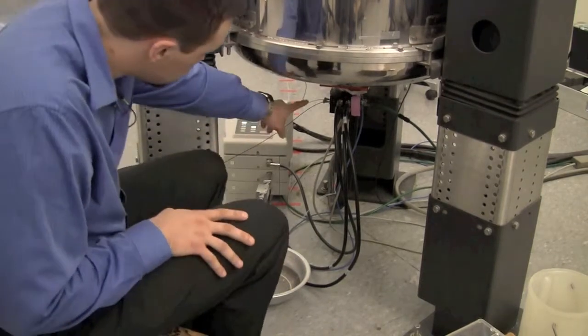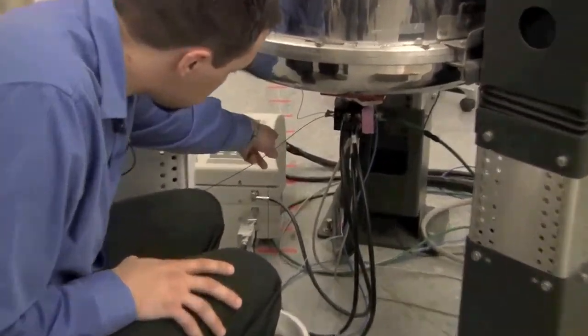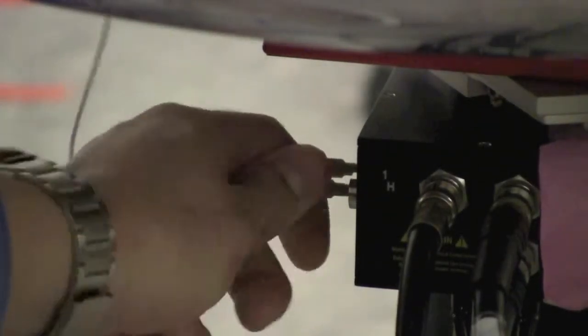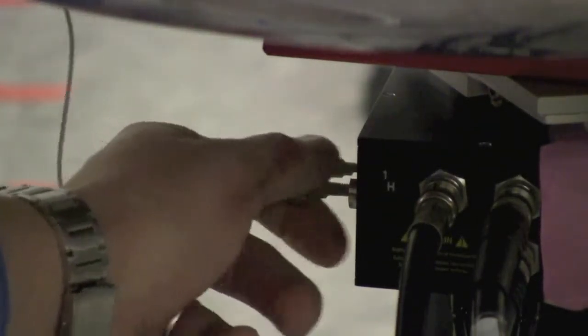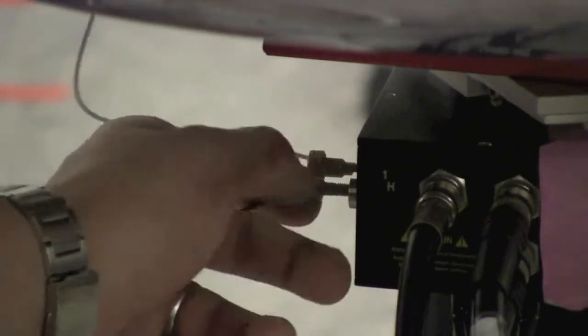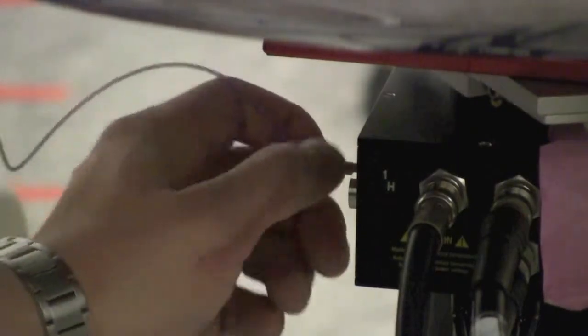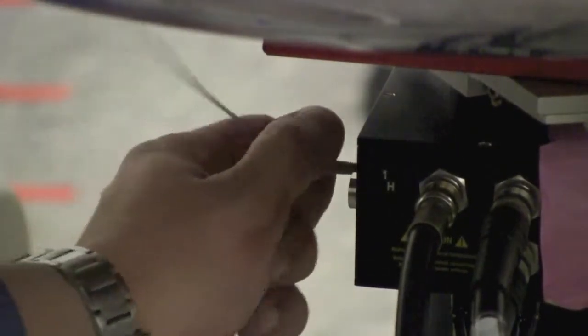And then we're going to disconnect the lines from the automation. So this black line is the input from the automation system and this purple line is the outlet. And then it goes in to the probe, up to the coil, and then back down and out. So we're going to disconnect both sides of it. So just unscrew it and try not to jostle the probe too much as you unscrew it. And you can just set these aside. And they may sort of twist around on you, that's okay.